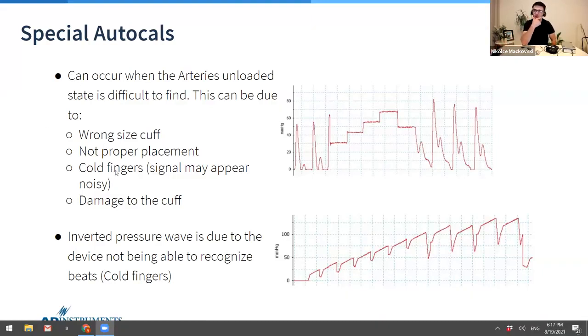Cold fingers, in my opinion, is probably the biggest culprit here. So my room here, I'm actually quite cold, so I'm trying to keep my hand warm as best I can before the demo. But naturally, if you have constriction within your arteries, within your fingertips, then this is obviously going to have an effect on how much light is actually being detected. Because if the system itself can't detect heartbeat, then what we're going to see instead is this inverted image here. So this here shows an example of if someone has cold fingers, then this sequence will arise until it reaches beyond systolic, and then it'll begin to actually show the readings. But even then, the readings may not be entirely accurate. So if you do have cold fingers, I highly recommend warming them up in some hot water before starting. So that really depends on the subject, but also the conditions of the room.